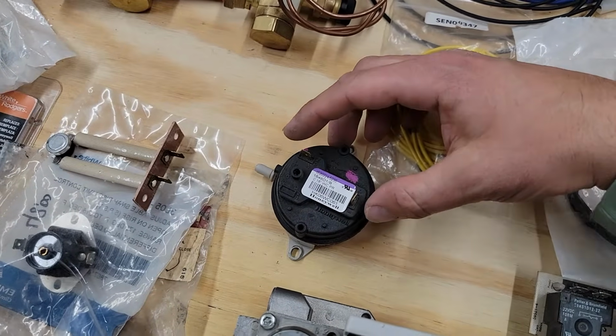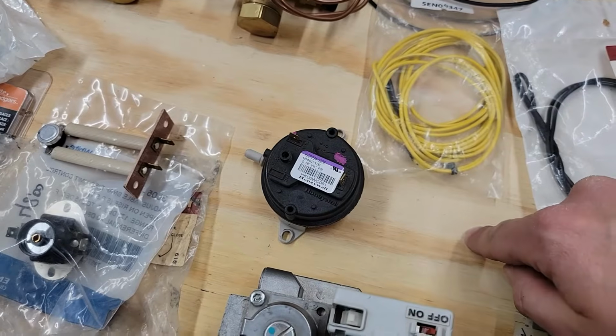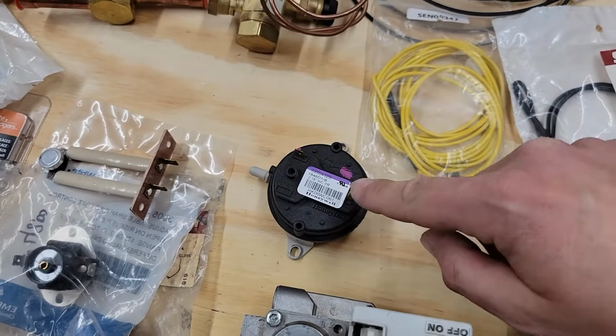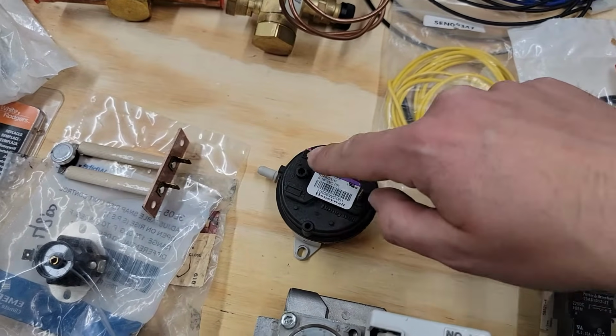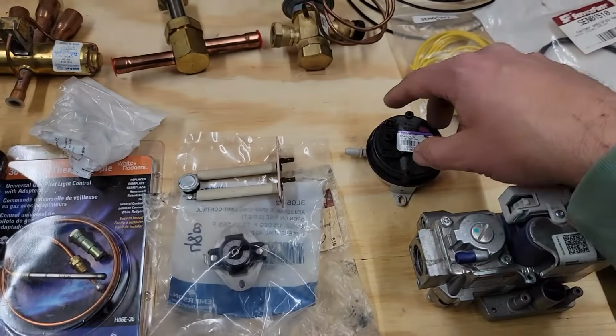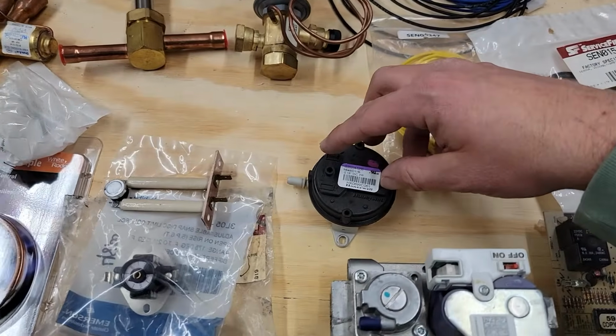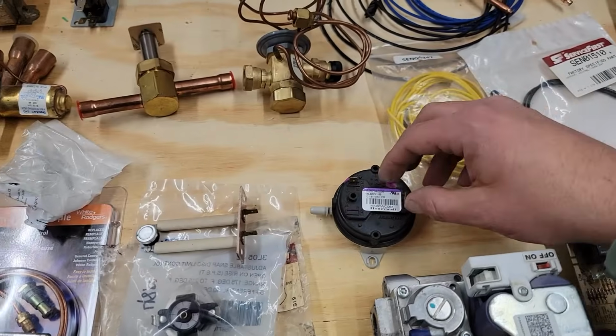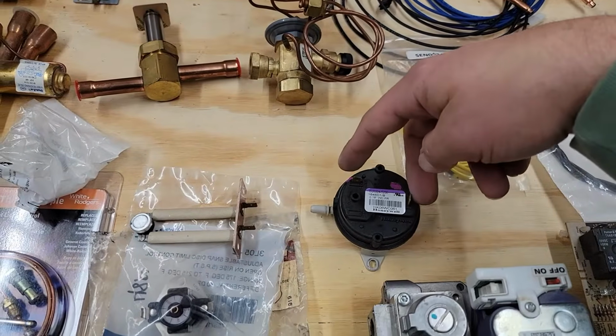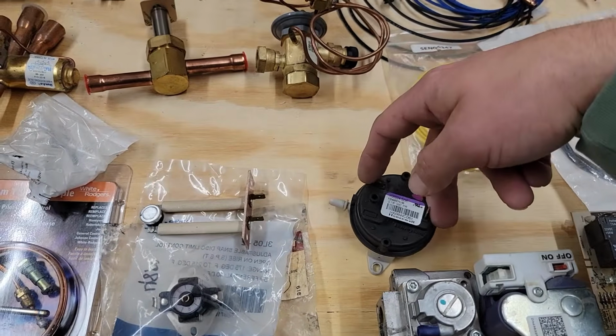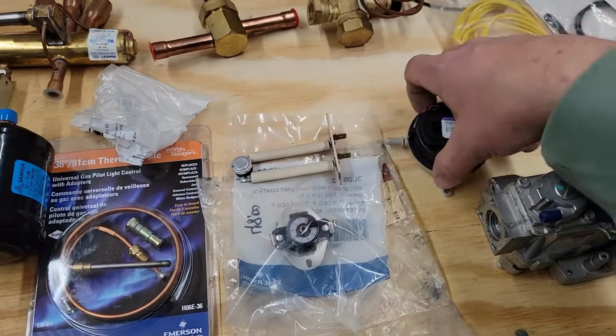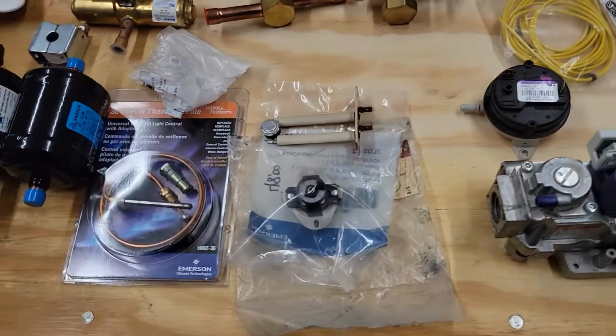You would take a meter, and you can check from your common or your ground in your equipment to each side to see if there's 24 volts going through this. Either that, or when the unit's running, you can take both wires off and then put your meter on ohms and then go across this and see if you have continuity. If you do, the switch is closed.